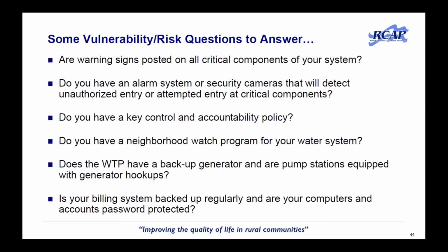Are warning signs posted on the critical components? We found, like I said, when we do these assessments, we go out and we look at the pump stations and we look at the tanks and we look at the water plant. And it's just kind of funny. It seems like there's several systems that don't really utilize warning signs much, and that can be one of the least expensive things a system can do, is put in some warning signs. So we try to suggest that when possible.